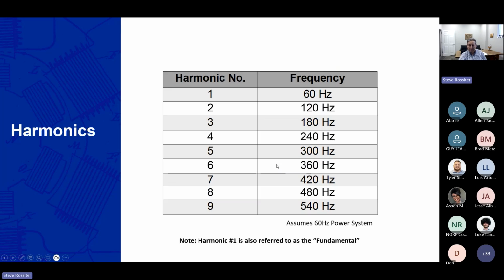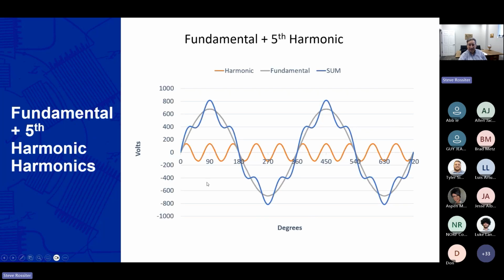And in the case of, I've removed most of the slides to not make this too technical of a presentation, but a simple depiction of this is your orange line is now the 300 hertz level, where the gray is my 60 hertz waveform. The resulting waveform is that blue line, which is an extreme level of harmonics in this particular case. If I were to mitigate that a little bit, it looked like two double humps, like you saw in one of those earlier pictures. And so there are some predominant frequencies that are developed based on the kind of solid state topology that your drive or welders or computers or power supplies or just about anything is going to experience.